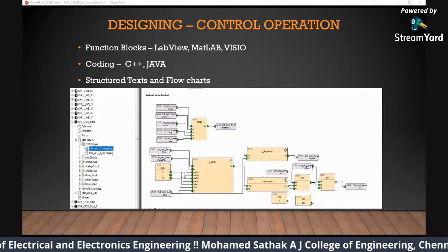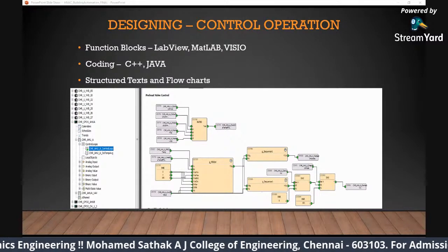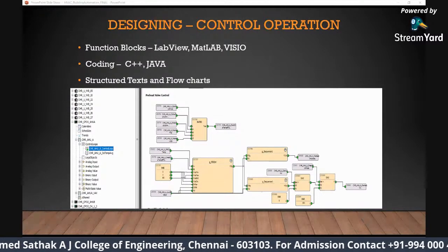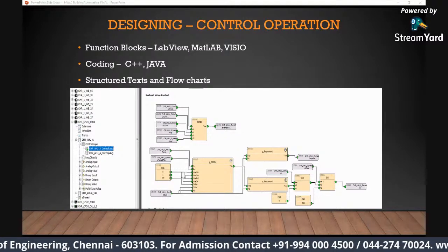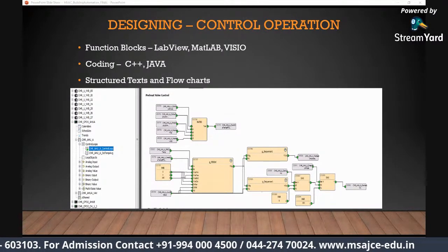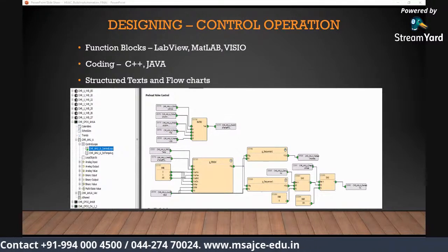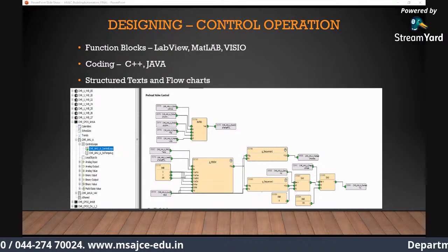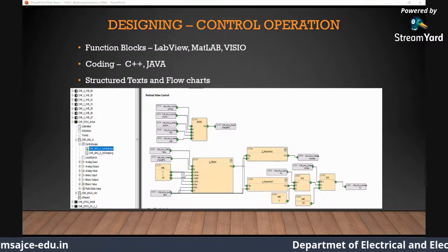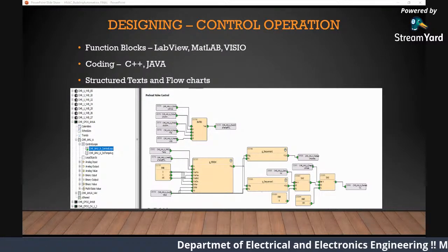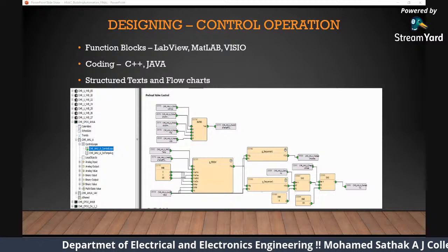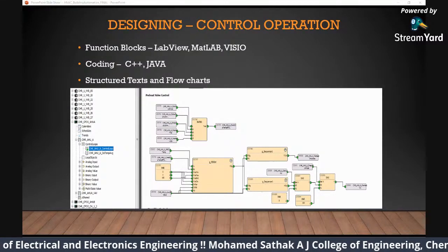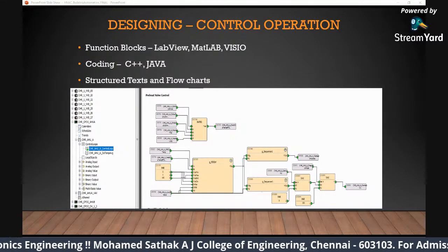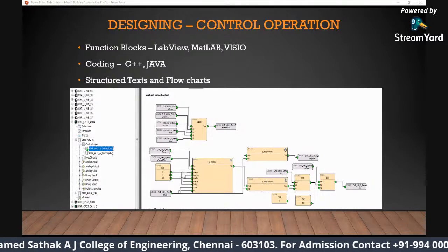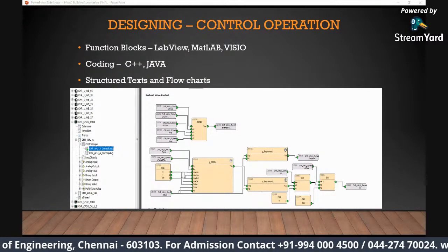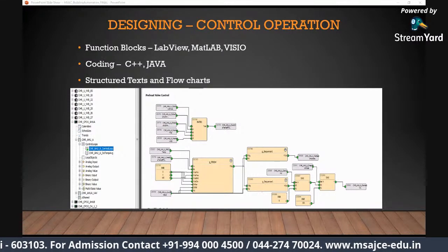So that's how your controller operates. It keeps on turning on. Everything should be designed in the designing tool, then downloaded into the controller. It takes care of its own. Your controller will not operate on its own. You have to design the sequence of operation. The sequence of operation is nothing but how your building operates. When should the AHU turn on? When should the light come on? When should your access door open? How does it decide, when you put the access card, which door opens? Who gives the access? Now I'm not just talking about HVAC, but also the fire system, security system, access door system, CCTV system.